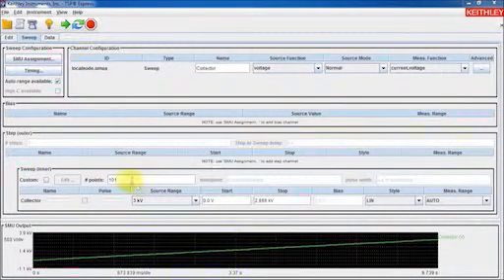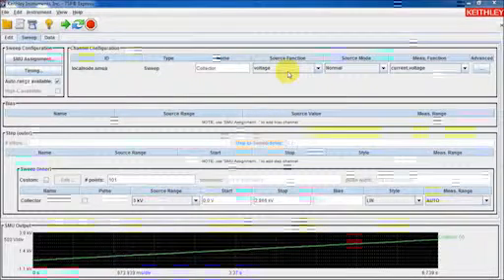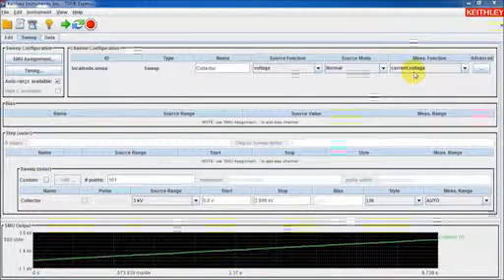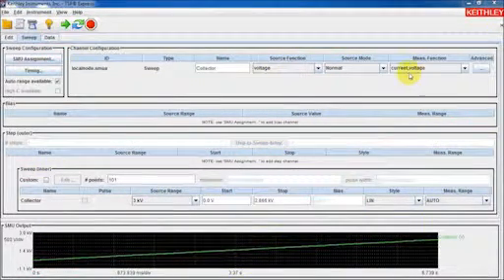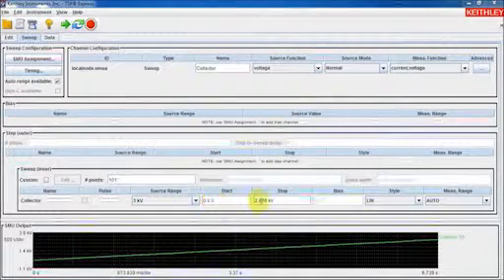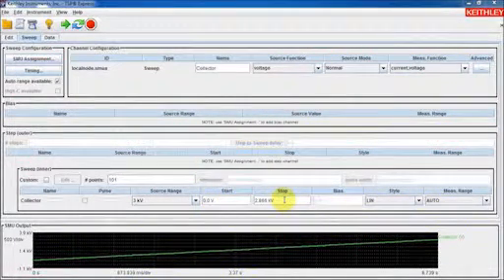Now, I've already configured the project to perform a 101 point linear sweep sourcing voltage and measuring both current and voltage. I've configured the sweep to start at zero volts and end at just over 2800 volts, right where the device just begins to break down.